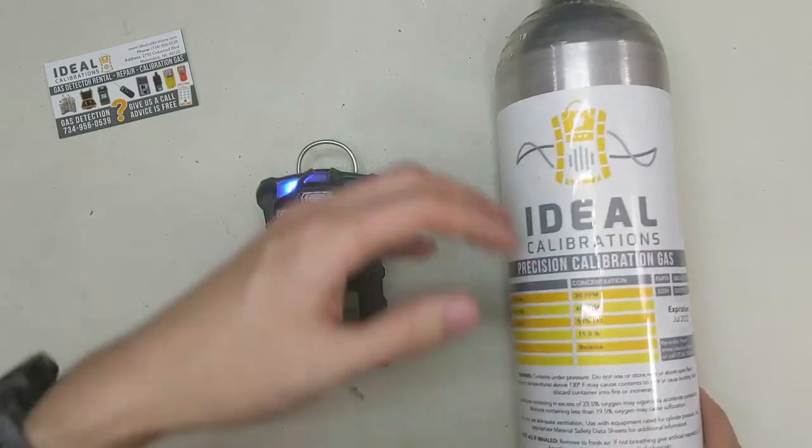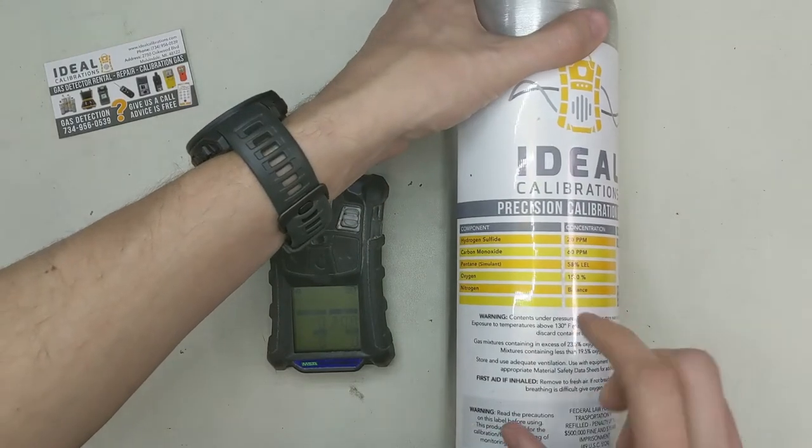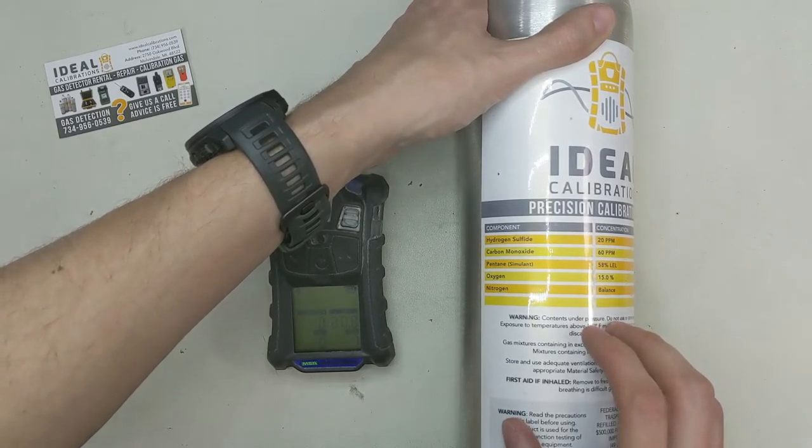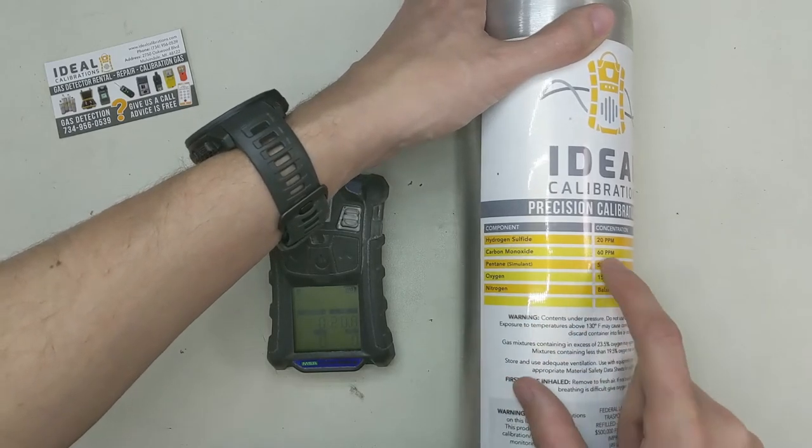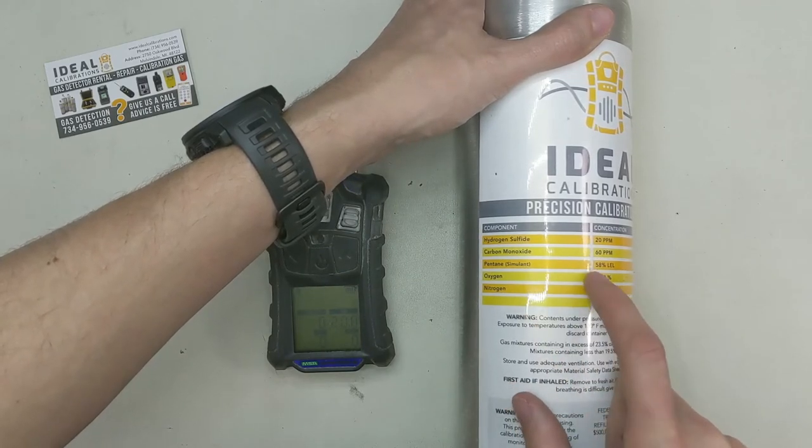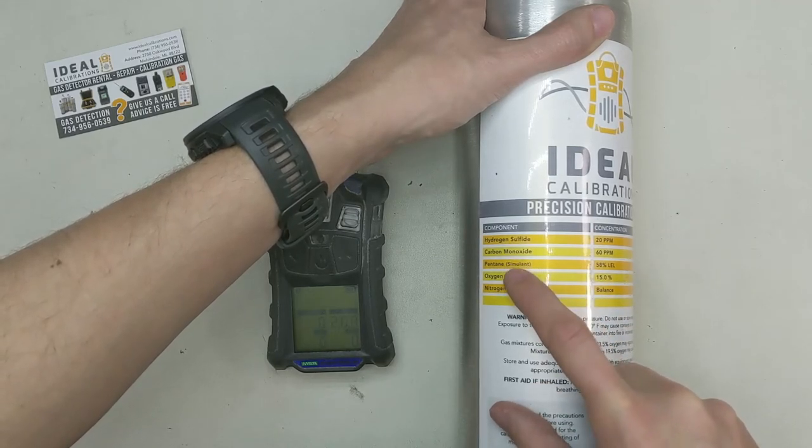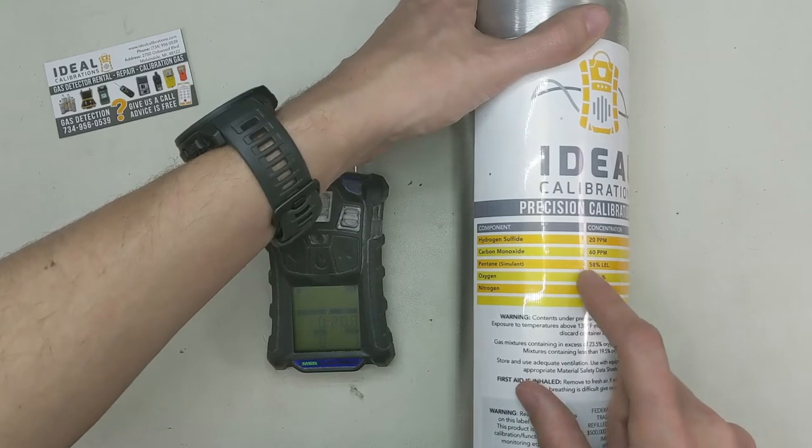Speaking of the gas, let's make sure you have the right cylinder. First thing to do is to check your components and make sure that they line up here with what we've got for it. So this is the default from MSA. If you've changed any of this, then you're going to need different calibration gas. But this is how it comes from the factory. So you have hydrogen sulfide 20 parts per million, carbon monoxide 60 parts per million, pentane simulant 58% LEL. Yours might say pentane simulant and it might say methane underneath that, and it would say at 29% LEL or 1.45% by volume. Either way, that's what we're looking for. In this case, those are all the right thing.